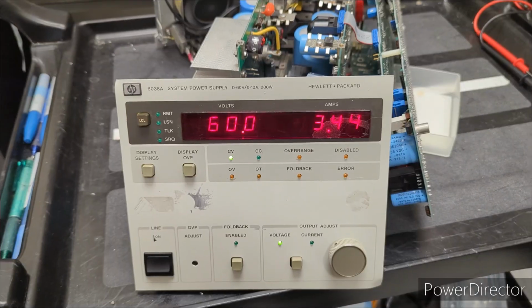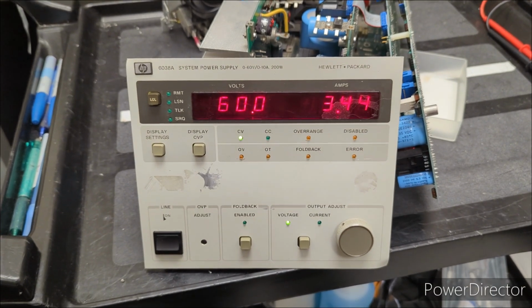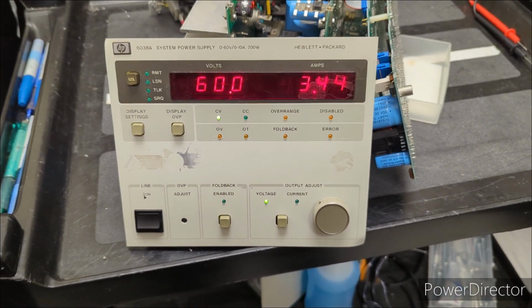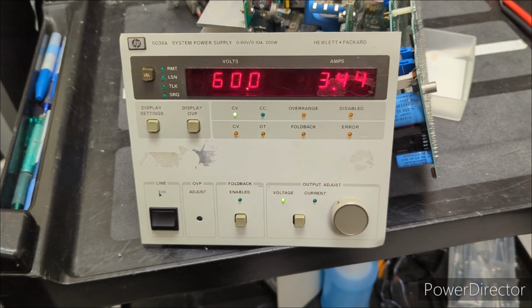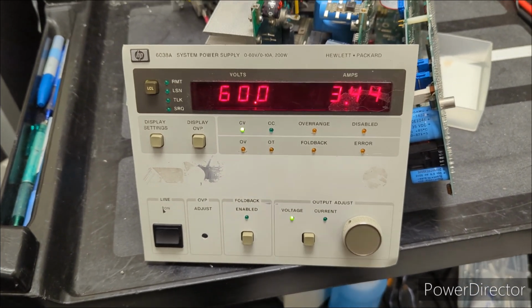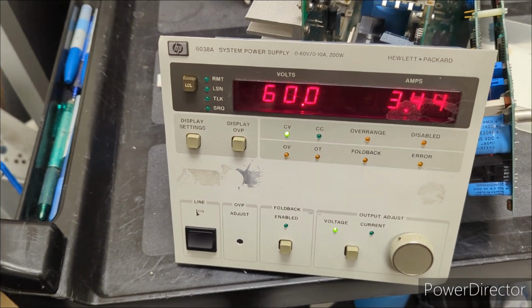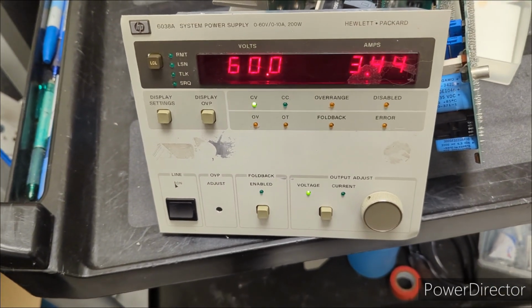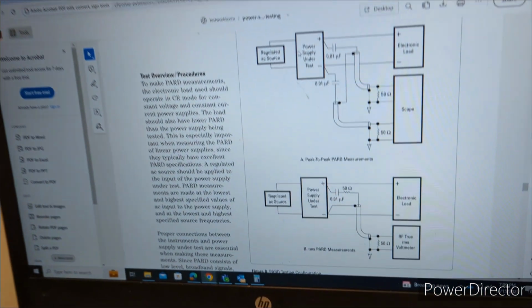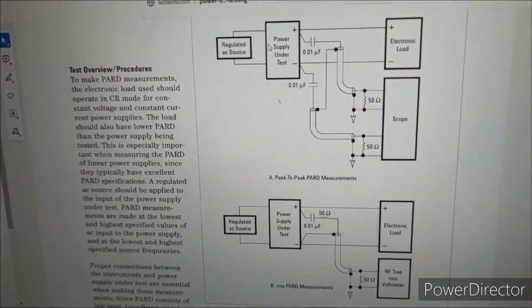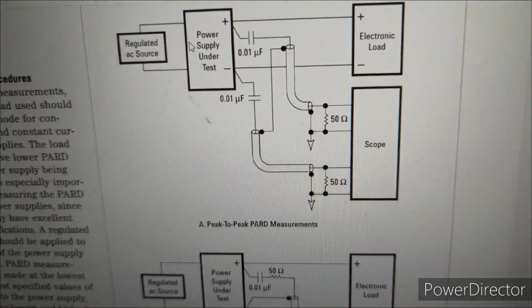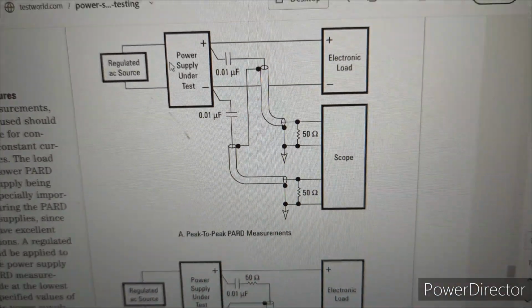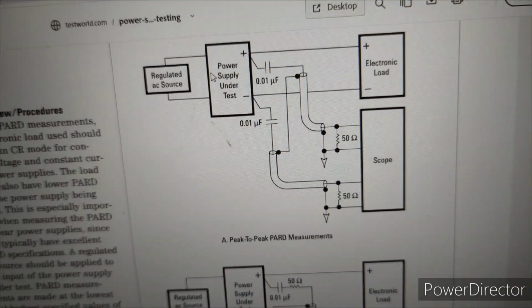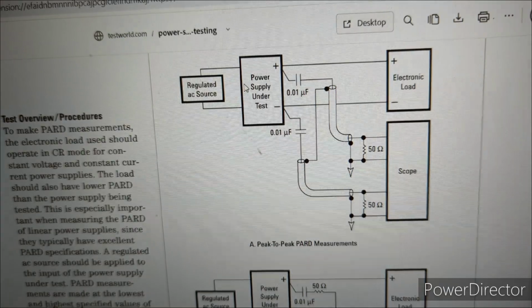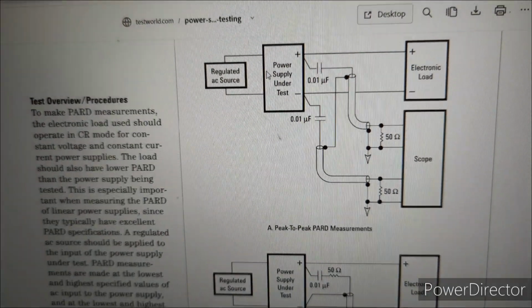Okay, so the next test I figured we'd do is a PARD test, which is periodic and random deviation, which used to stand for ripple and noise. But that's basically what we're looking for here on the output under a load. Looking at that Agilent document, the service manual has a similar setup where you have these coaxial cables with a 50 ohm termination connected to the outputs of the supply, and they've also got blocking capacitors on the output.